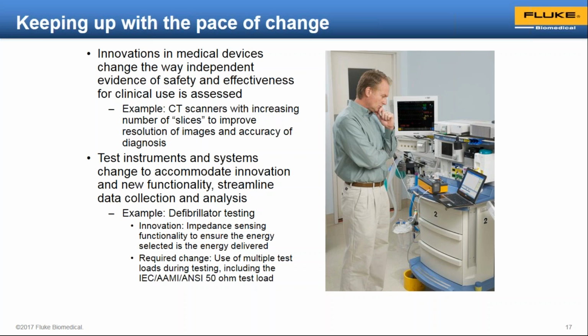We can call out CT scanners, we can call out defibrillators, where we have more and more a shock advisory, if not an AED functionality, where the device itself is designed so that it can sense the impedance of the patient's chest and adjust the output energy of the defibrillator according to the impedance that it sees, so that there's enough current delivered through the tissue from outside to inside to make sure that the heart is properly defibrillated when the time comes, when it really matters.